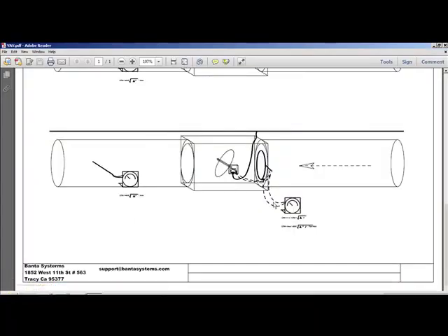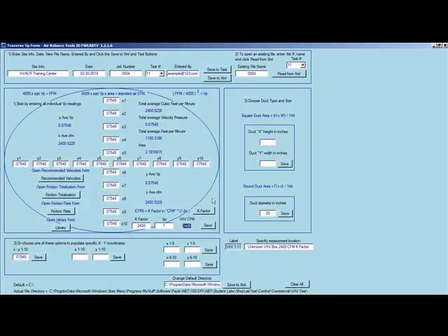So now that we've recorded that and we know this is a 2400 CFM box, we'll go ahead and reconnect the controller, and release the fan so now it can control, and we'll take our reading at our maximum CFM cooling set point. Say at our maximum cooling CFM set point we recorded a 0.75.